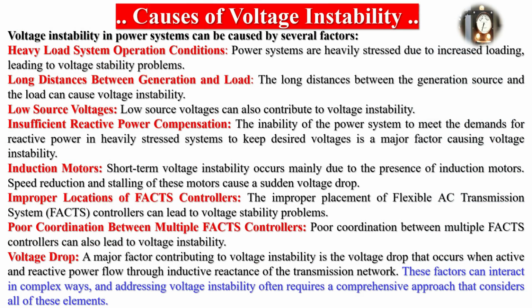Let's discuss causes of voltage instability. Voltage instability in power systems can be caused by several factors, like heavy load system operation conditions. Power systems are heavily stressed due to increased loading, leading to voltage stability problems. Long distances between generation and load. The long distances between the generation source and the load can cause voltage instability. Low source voltages. Low source voltages can also contribute to voltage instability. Insufficient reactive power compensation. The inability of the power system to meet the demands for reactive power in heavily stressed systems to keep desired voltages is a major factor causing voltage instability.